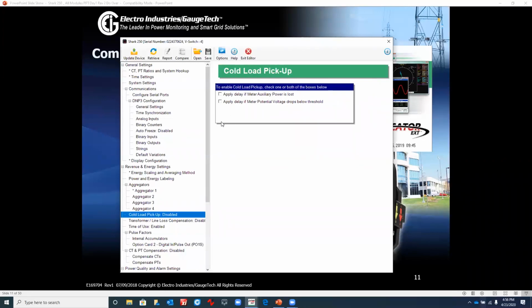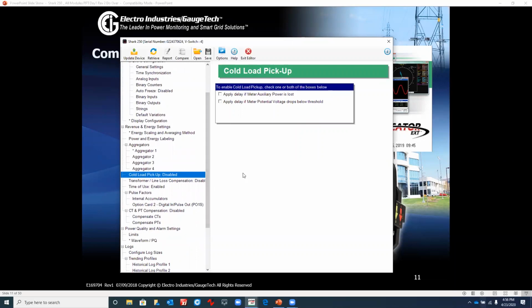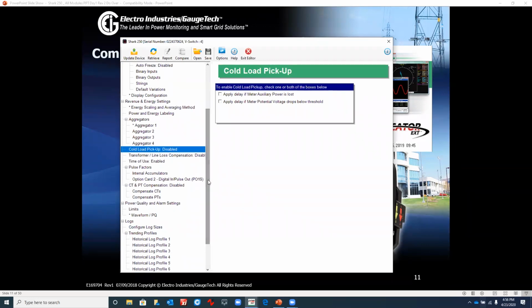Cold load pickup. This is a feature that we turn on and turn off. Basically, from a utility point of view, you may want this because you may want to defer or not penalize a customer shortly after power has been restored during an outage. So you want to defer a certain amount of time. Typically, industrial customers would benefit from something like this, where as power was restored, the peak wouldn't slam in the first interval, and the customer would be penalized for that interval. So you would enable that. A lot of utilities use this option, and it varies from utility to utility how much of a period you want to defer, and we call that cold load pickup.